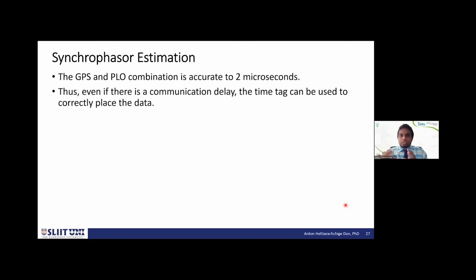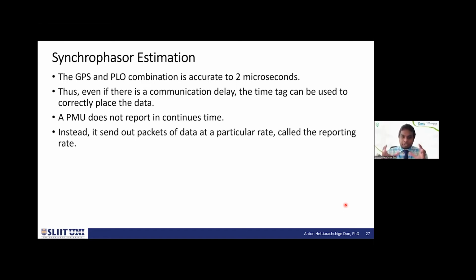The point is that because it's transmitting data containing the time it was taken, even if there's a communication delay, we can use the time tag to place the data correctly at the receiving end. So the PMU doesn't report in continuous time. What it does is send out packets of data at a particular rate. This is called the reporting rate.